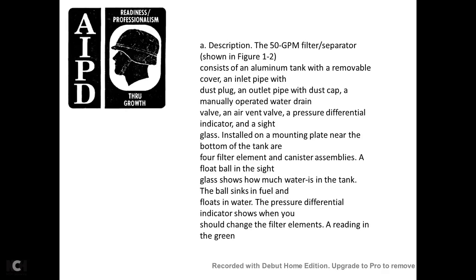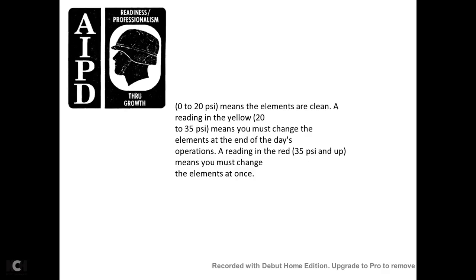The pressure differential indicator shows when the filter elements should be changed. A reading in the green, 0 to 20 psi, means the elements are clean. A reading in the yellow, 20 to 35 psi, means they must be changed at the end of the day of operation. A reading in the red, 35 psi or up, means you must change the elements at once.